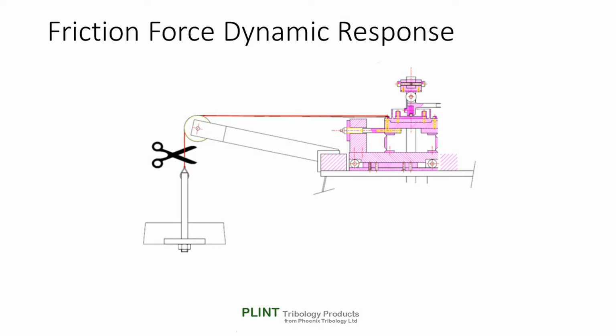Confirmation of this resonance effect and measurement of the test assembly's natural frequency can be demonstrated by a simple experiment, the system response to a step change input. A mass is attached to the transducer assembly by means of a string and a pulley arrangement. Cutting the string plucks the assembly. Measurement of the period of oscillation from both the friction signal and the plucking experiments indicates a resonant frequency without friction damping of approximately 830 Hz. In other words, so close to the calculated value to be beyond doubt.